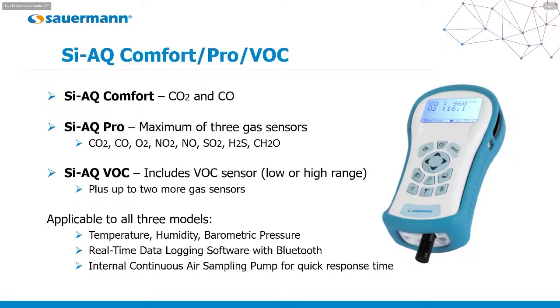Now, in addition to the gases, which is the main feature of these models, as you can see below, they can all measure air temperature, relative humidity, and barometric, also known as atmospheric pressure. They all come with real-time data logging software with Bluetooth. So for example, if you're in a certain building and you want to do a 24-hour monitor because you might be concerned that certain hours of the day there might be higher levels of some of the pollutant gases, with the logging software you can set it up and automatically log data for a day or even longer. And you can set it up, for example, to save data every 10 minutes, 20 minutes, every hour. You have a lot of flexibility with that.